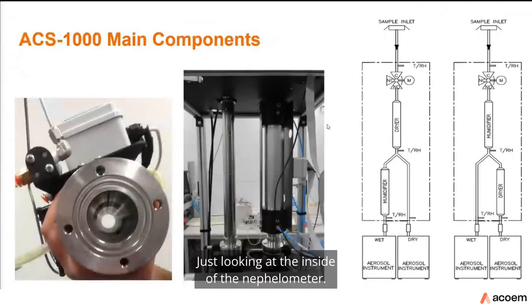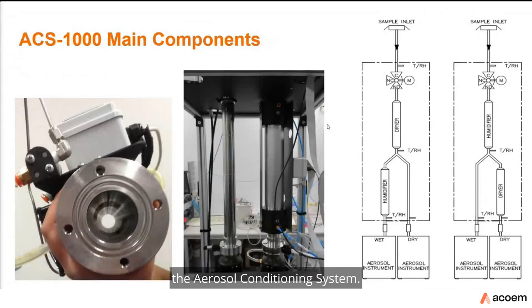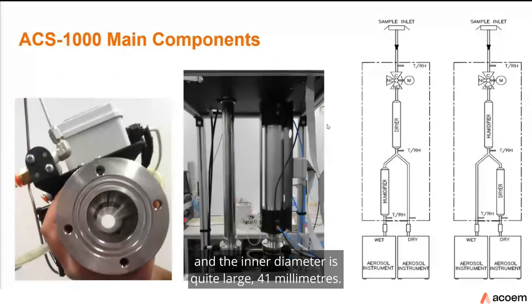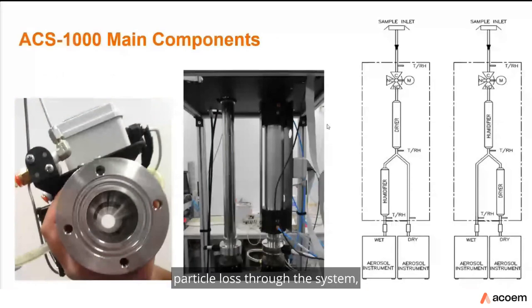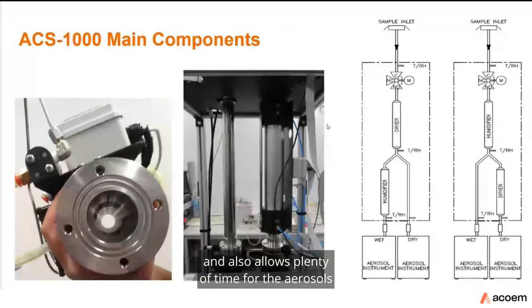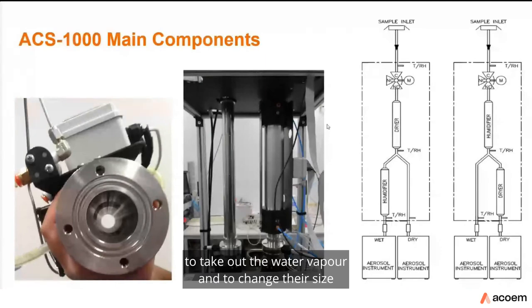Inside the aerosol conditioning system, it is made of electropolished stainless steel with a relatively large inner diameter of 41 mm. This ensures minimum particle loss through the system and allows plenty of time for aerosols to take up water vapor and change their size and state as they pass through.